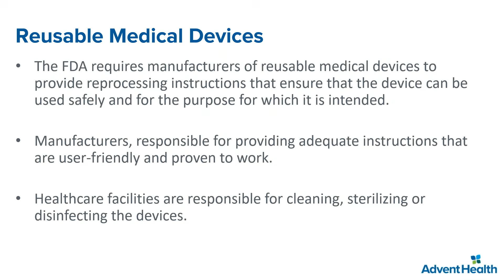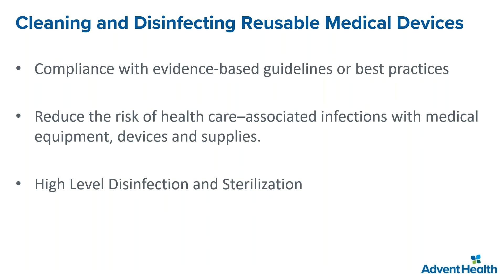So the infection prevention specialist, the infection prevention nurse, needs to know all the policies regarding the reprocessing of medical devices. In cleaning and disinfecting reusable medical devices, compliance with evidence-based guidelines or best practice is the law. We have to reduce the risk of healthcare-associated infections with medical equipment, devices, and supplies, and we use either high-level disinfection or sterilization. I am not going to cover a lot of information regarding high-level disinfection. However, I'm going to talk more about sterilization because my friend Tiffany already covered high-level disinfection.